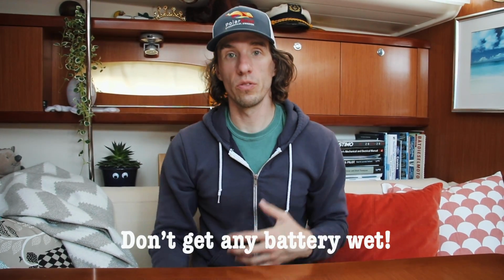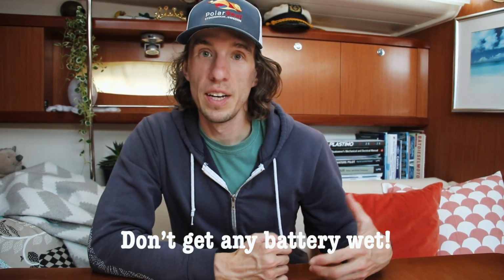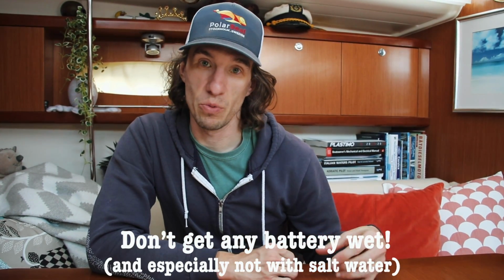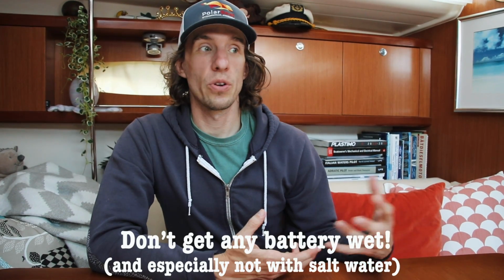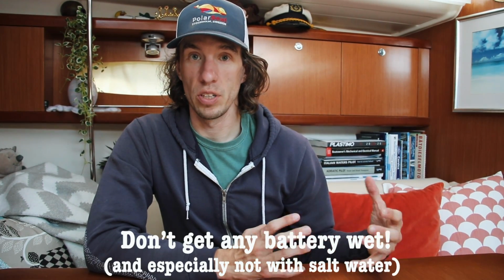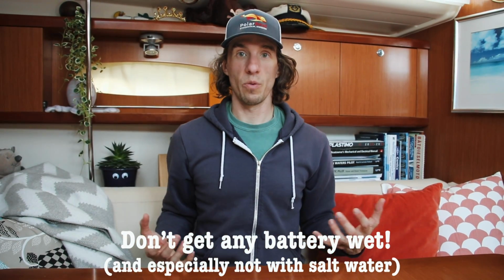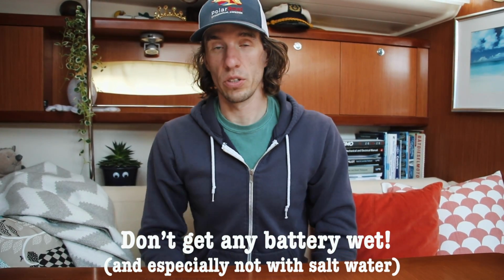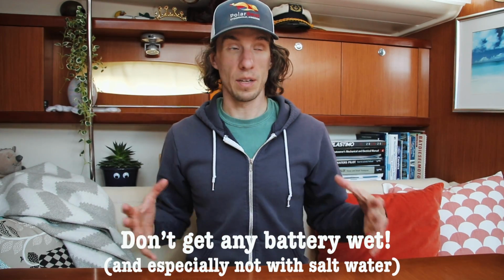Just like any battery, you do not want to get them wet or submerge them in water, specifically salt water, and that goes for lithium as well. You could place them in a bilge as long as that bilge is primarily dry. If you have a constantly wet bilge, I would advise against it. I'd also make sure those batteries are in a box anytime they're placed anywhere on the boat. The marine environment in general is not a problem, so if your batteries are in a box with a top on it, a little bit of salt in the air while sailing isn't going to be an issue. Maybe just clean off the terminals every once in a while like you would with lead acid, but generally it should be okay.